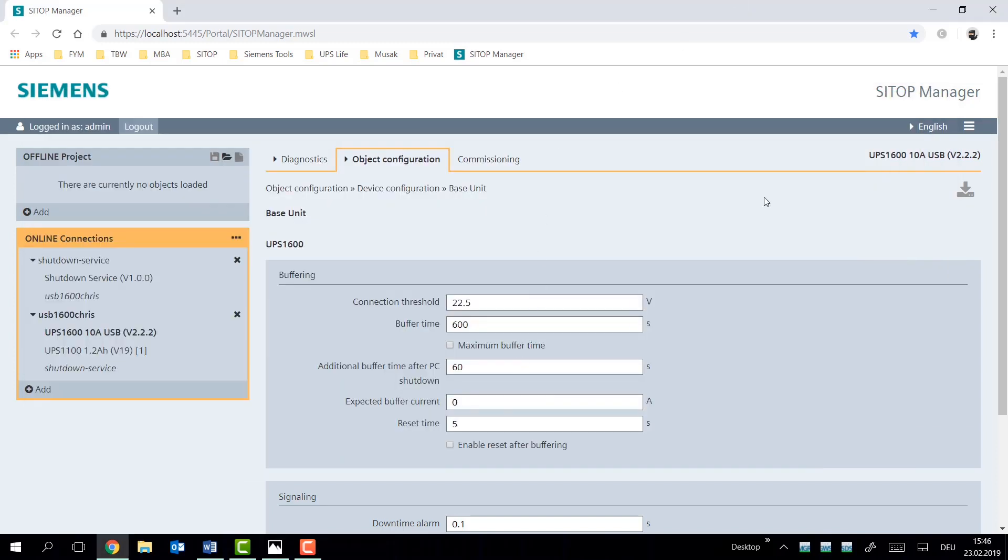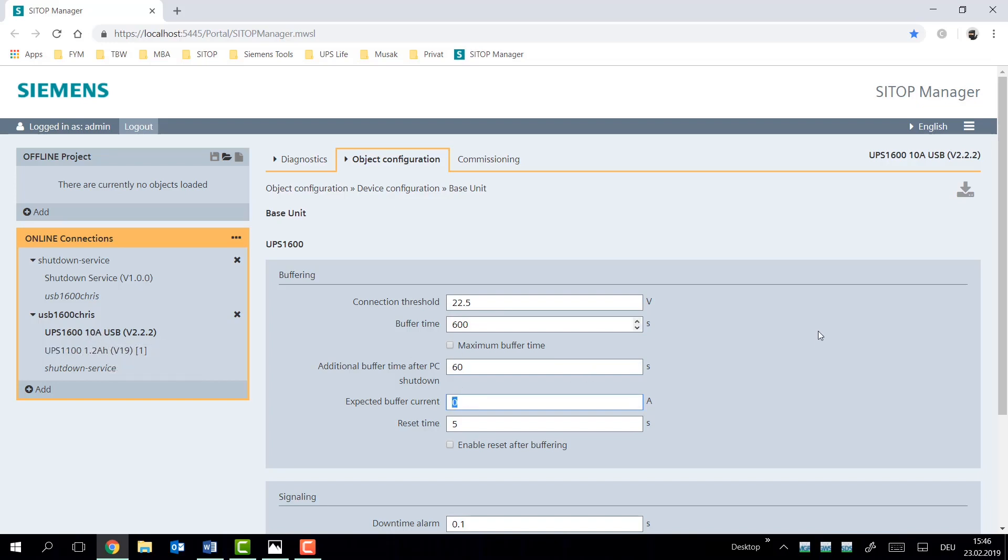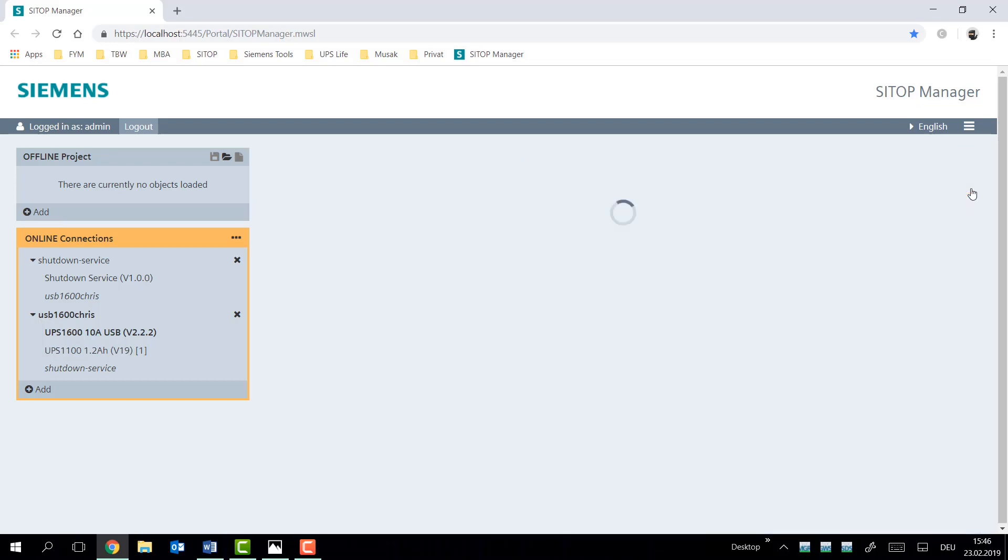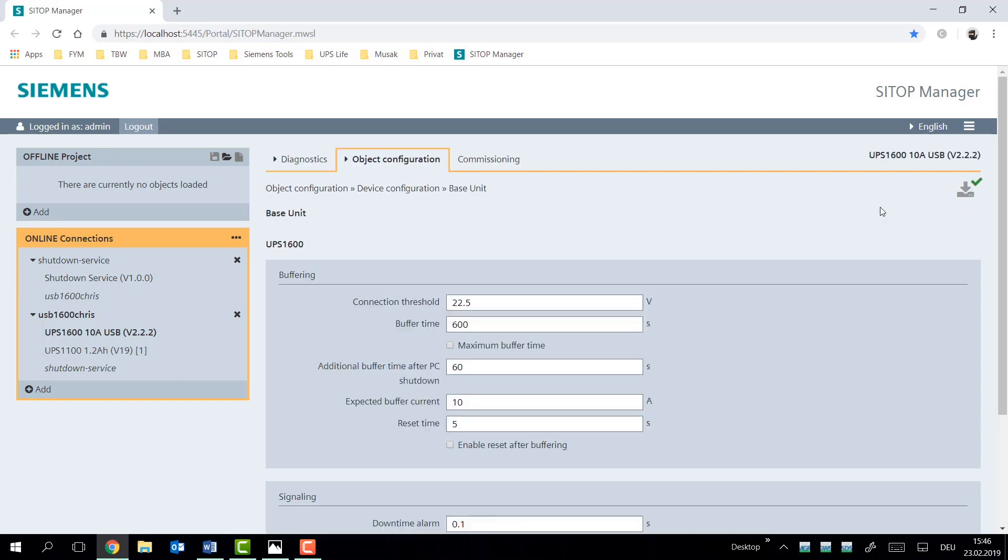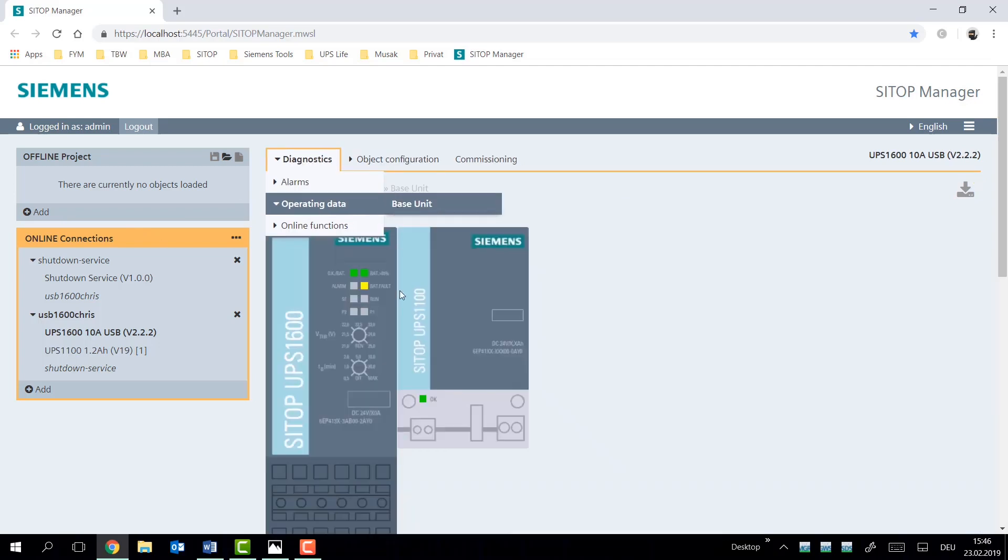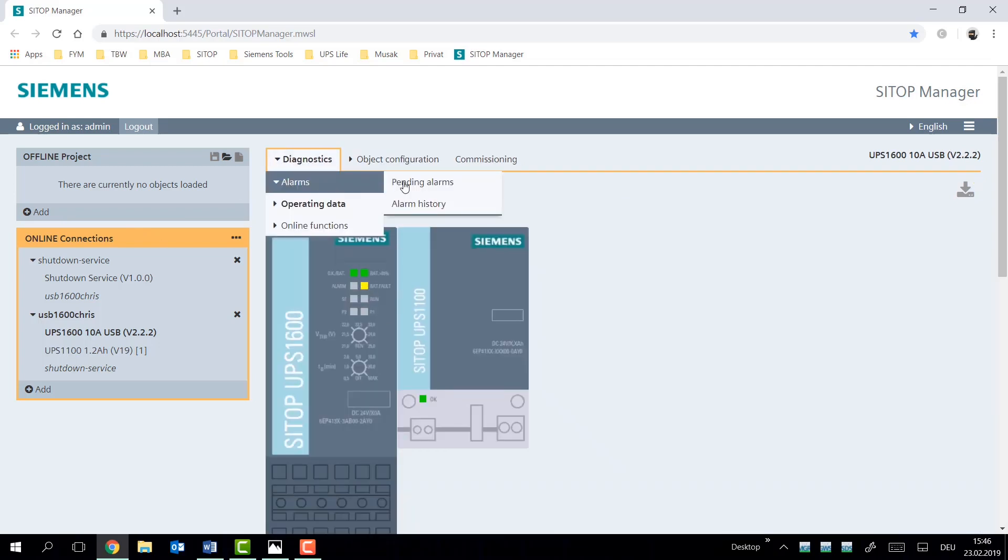The expected buffer current is an optional parameter to help you with the engineering of your system. Now, in this case, we have a threshold at 22.5 and a buffering time of 600 seconds set. Now, this is a 10 ampere UPS device, and I know that with a 1.2 ampere hour, it will never be able to buffer 10 amps at 600 seconds. That's just simply too much. But if we enter that value in, what it'll do is give us feedback on the device itself.